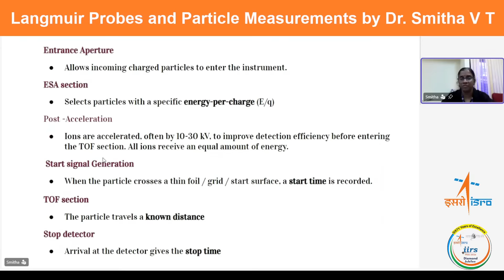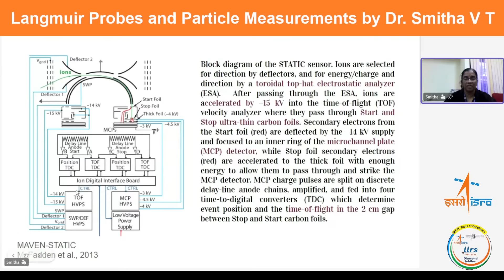This is such a system, from the MAVEN STATIC instrument, for the Mars mission by NASA. You can see that in the entrance apertures there are some deflectors which tell about the direction. Then for the energy and charge there is an electrostatic analyzer section, followed by a time of flight section, after which the post acceleration is by minus 15 kilovolt, and the detectors are MCPs. You don't have to go into the details. As I told, there is a thick foil and a start foil. From the start foil to the thick foil, the gap is 2 centimeters, and the time of flight in this 2 centimeter region between the start and stop carbon foils is used to measure the mass of the particle. The time signals are converted into digital, and the other controllers and high voltages for this instrument are given here.